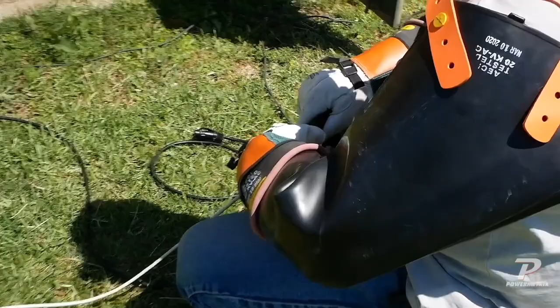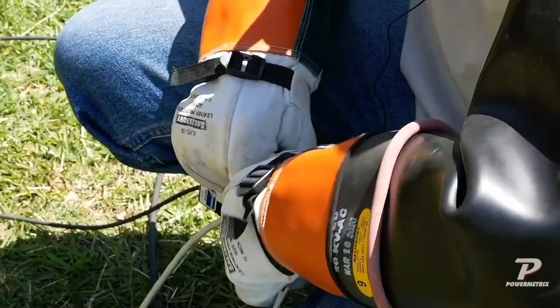He's making the connections now with the cable, connecting it up. This is where, when you're out in the field, something might happen to it, you broke it, bent it, or did something to it, or a connection after a while from connecting and disconnecting a lot, the pins on it, whatever it is, you might have one phase on your cable that's gone bad.